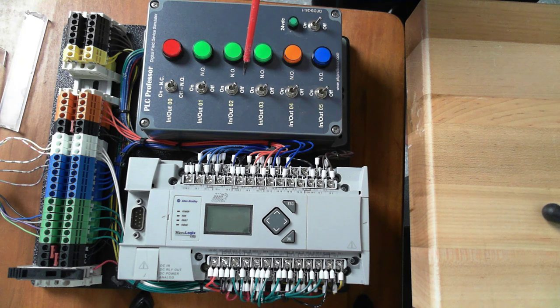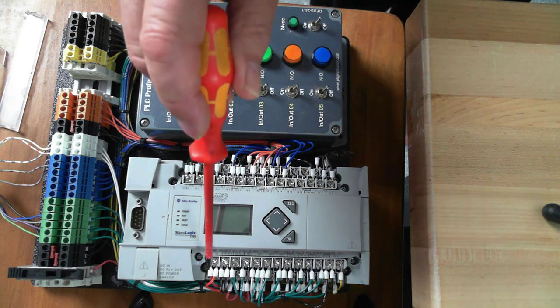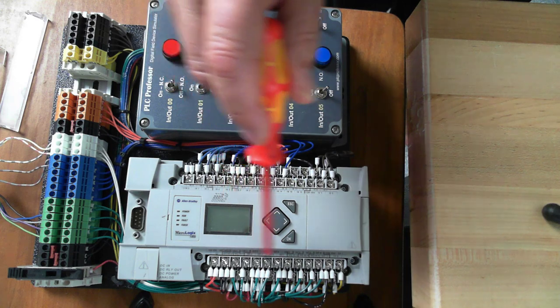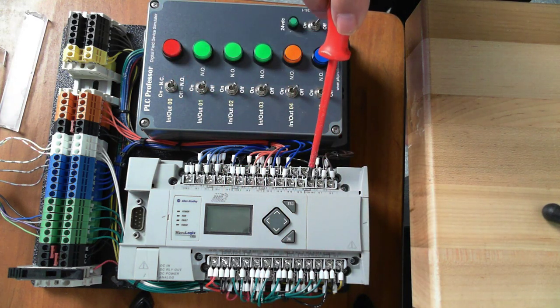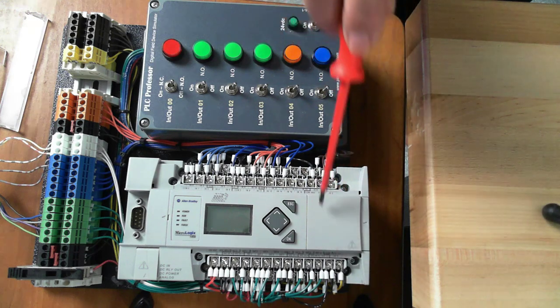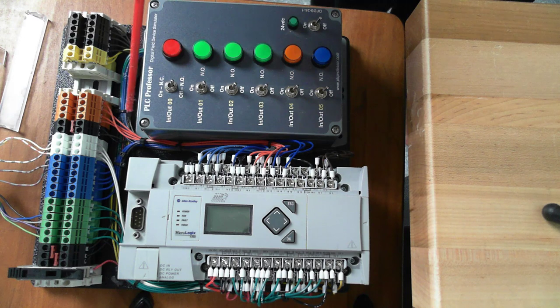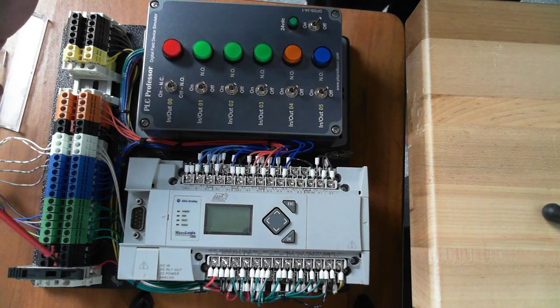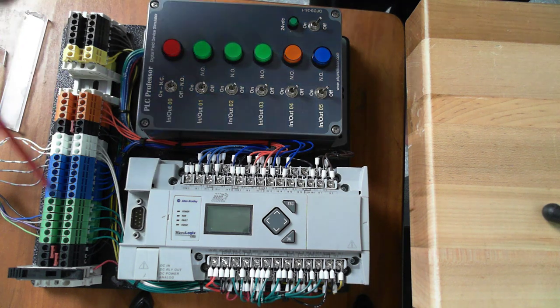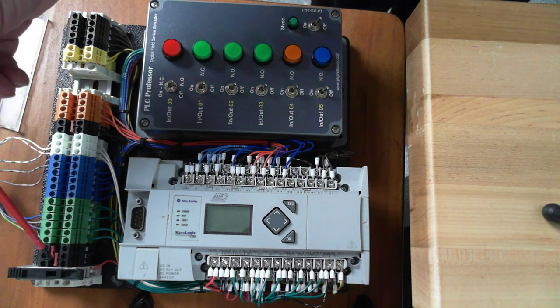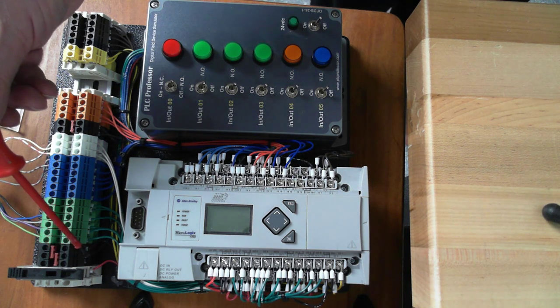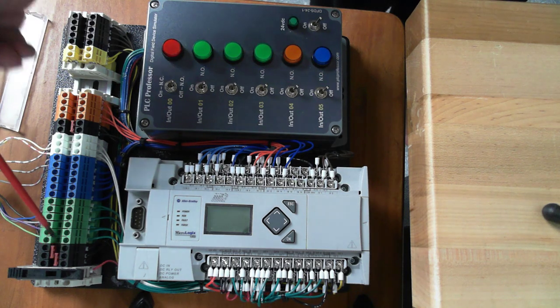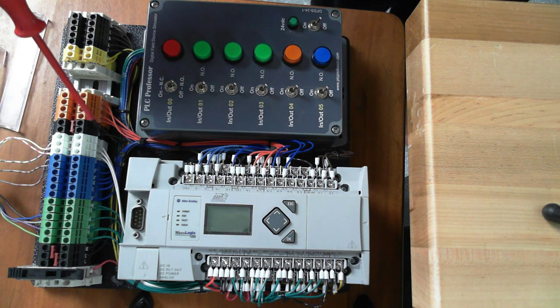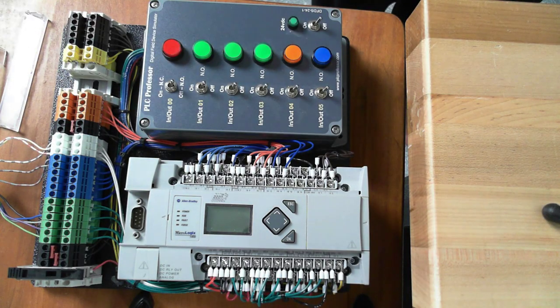However, we do have a common 0 volt DC, and it really doesn't matter where it starts, whether it starts here or starts here. All of the commons, even the common for the analog here and the common for the analog there, all of those black wires are hooked into one common 0 volt DC bus, and that includes all of these black terminals here and here. They're all connected together, and I see the little jumpers in there, so we only needed to bring in one black conductor here to make all three of these 0 volts DC and one conductor here. But we're using all of these different screw terminals to land common 0 volt DC voltage points.